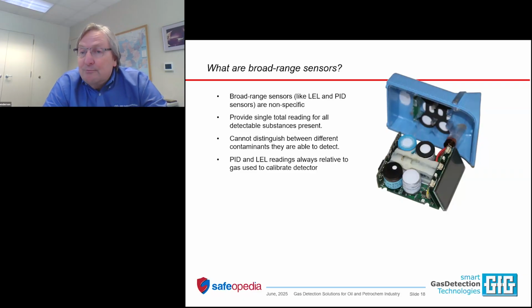You get one reading. For the PID, the way it detects is you shine a beam of ultraviolet light through a sensing chamber and you ionize the target molecule. You strip an electron. That produces an electrical current that is proportional to the concentration of gas. And you can have a mixture of many kinds of gases. You get one electron from each of the molecules that's present at that moment in the optical sensing chamber. So you get one signal for the entire mixture of VOC gases. So it's a broad range sensor. The sensors cannot distinguish between different contaminants they're able to detect.